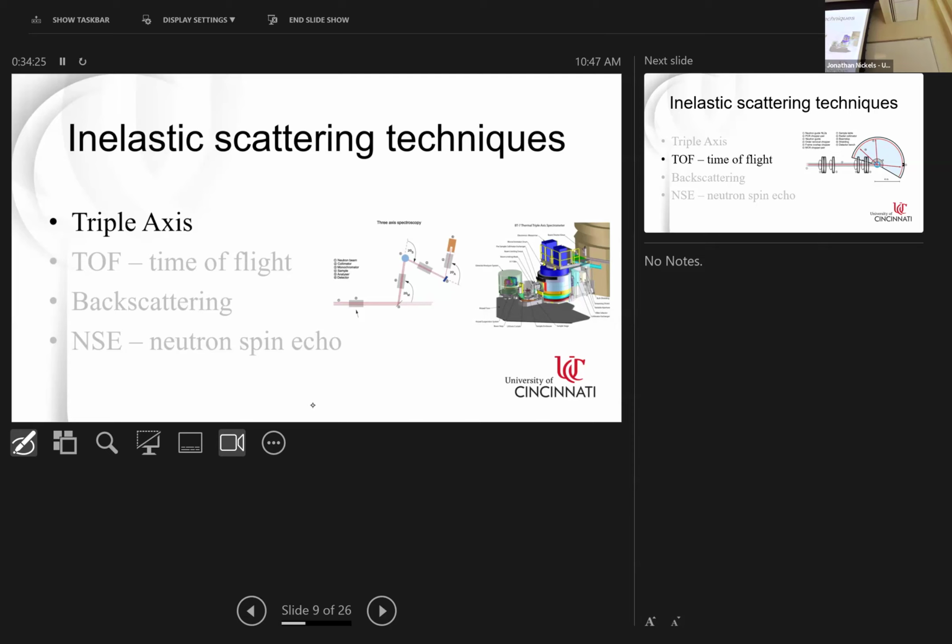You then take that off the sample at a certain angle that you care about, right? So there's some wave vector you care about, and what you're going to do is spin this. This is an arm. There are 2 arms, and you change the angle to see the scattering wave vector change. Then you have an analyzer crystal here at the end that is also reflecting a single wavelength.